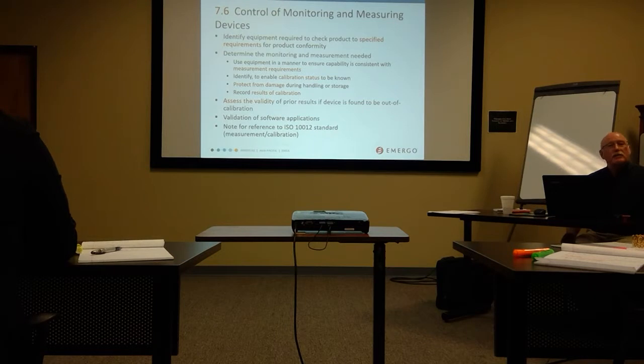I said, okay, folks, you have a choice. Choice A, pick up the phone, call the FDA, tell them that you have no way of knowing whether the lasers that are being pointed into people's eyeballs are within the calibration specs or not, and be prepared to recall everything you've made in the last year, which would have put these guys out of business. Relatively small company, there's no way they would have withstood this kind of recall. Choice B, you better go find yourself a laser physicist who's going to prepare for you a very nice report that says no matter how far out of calibration this laser is, it can't physically produce enough power to cook your eyeball, which is what they ended up doing, fortunately for them. The alternative would have been a massive recall. They would have been out of business.